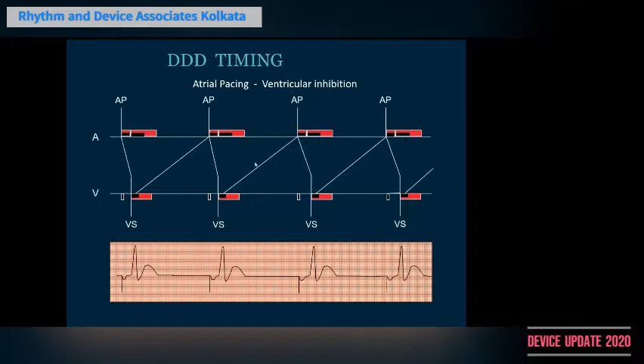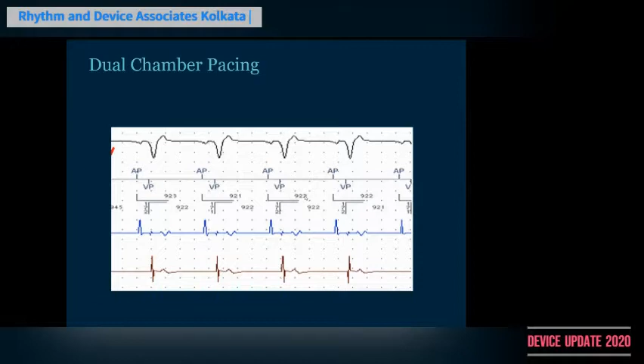So next is dual chamber pacing. Suppose we have both chambers being paced, so you have an AP and a VP. Look at the second line, the marker channel. You have AP, VP going on at pre-specified intervals. The interval between the AP and VP is somewhere around 170 milliseconds, which is marked in this ladder diagram. And after that ventricular pacing, there is a refractory period which corresponds to a total refractory period of 922 milliseconds. So you can actually estimate the ventricular refractory periods from these values.